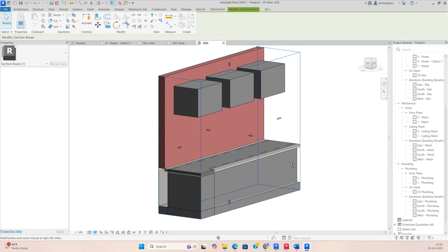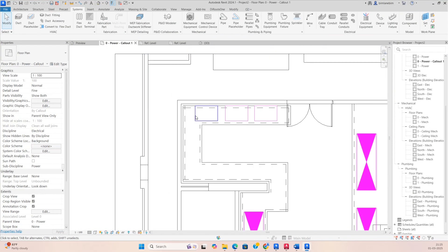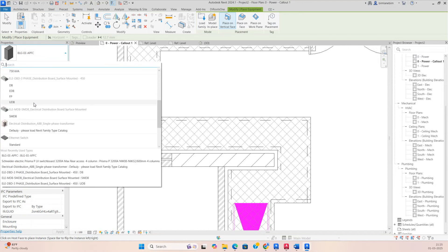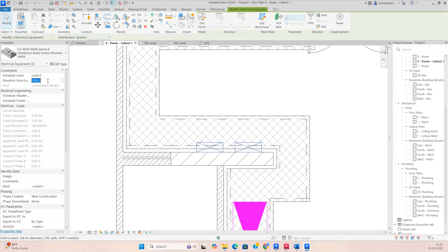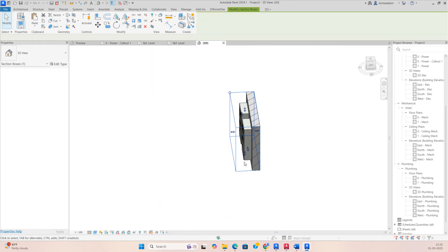You can also place other electrical equipment like DBs and SMDBs. Go to Electrical Equipment, select the SMDB family, and place the SMDBs here. You can change the elevation — I'm setting 2200mm for this area. Look in the 3D view and you can see they are also fixed correctly.